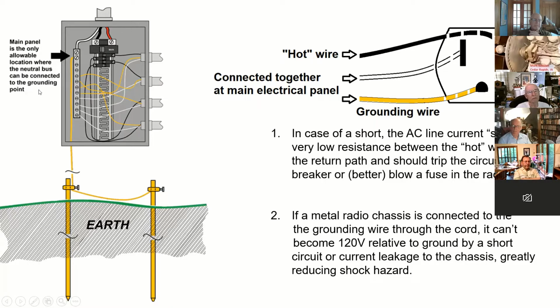And this is the only place where the neutral bus can be connected to the grounding point, in the original panel coming in. The reason is that if there's an open circuit somewhere, either accidentally or because somebody's working on it, you could back feed 120 volts to a neutral that's broken, and then you grab hold of the white wire and get a shock. If there's a short circuit, again, to your refrigerator, radio, or whatever, it actually goes to the ground wire, which goes back to the neutral, which causes a short circuit to be seen between either of these hot wires and neutral. And hopefully that's supposed to trip the circuit breaker, basically.